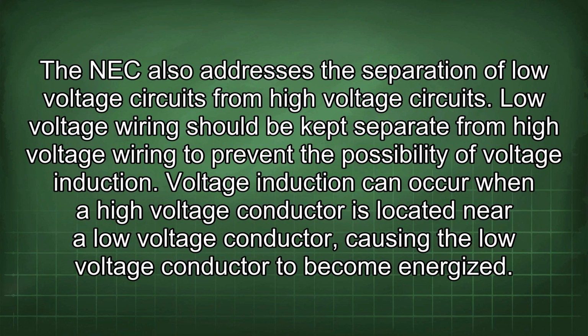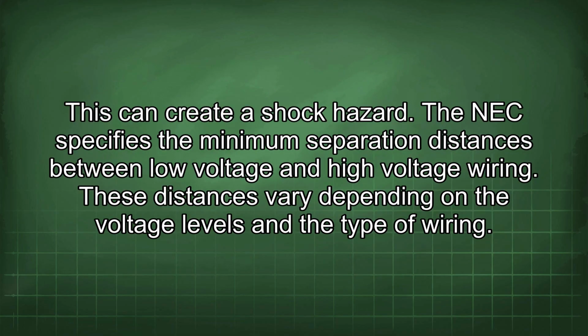The NEC also addresses the separation of low-voltage circuits from high-voltage circuits. Low-voltage wiring should be kept separate from high-voltage wiring to prevent the possibility of voltage induction. Voltage induction can occur when a high-voltage conductor is located near a low-voltage conductor, causing the low-voltage conductor to become energized. This can create a shock hazard. The NEC specifies the minimum separation distances between low-voltage and high-voltage wiring. These distances vary depending on the voltage levels and the type of wiring.